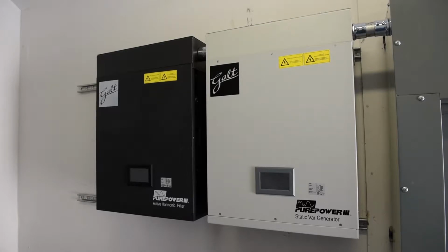In this video, we're going to show you how to program the Galt Pure Power 3 Static Var Generator, or SVG, and the Galt Pure Power 3 Active Harmonic Filter, or AHF. In this particular installation, the customer had low power factor and thus was getting power factor penalties from the utility. In addition to that, he had harmonic distortion, which was polluting the quality of his power system.